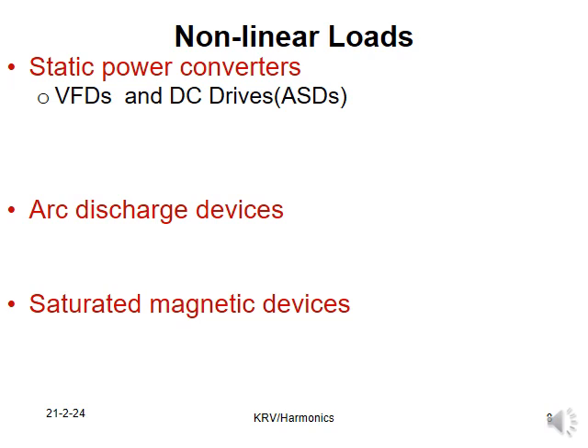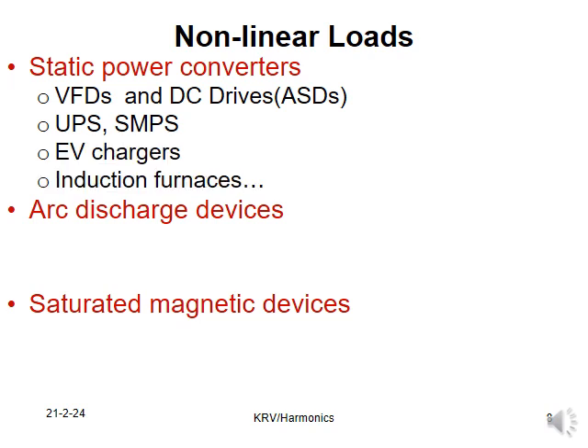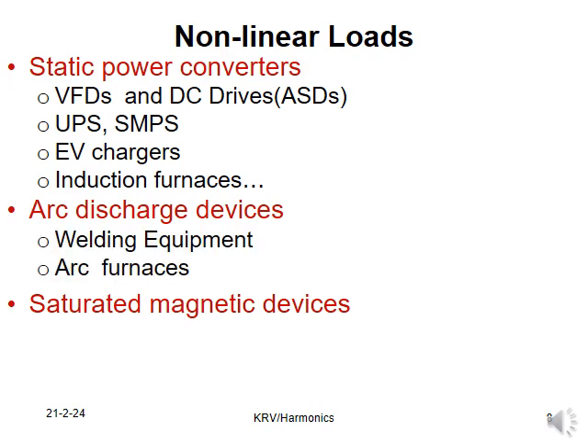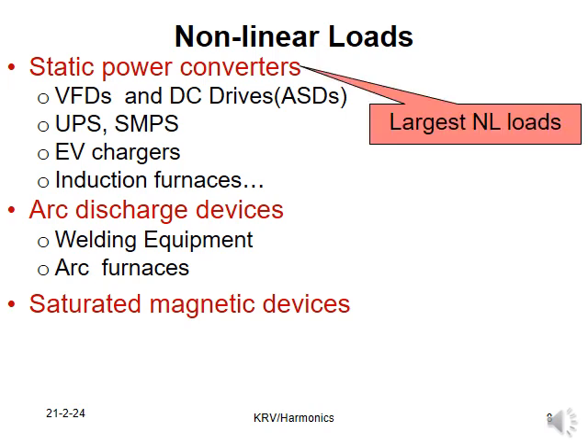Variable frequency drives and DC drives, which are generically known as adjustable speed drives, uninterruptible power supply and SMPS, EV chargers and induction furnaces belong to static power converters. Welding equipment and arc furnaces belong to the category of arc discharge devices. The static power converters are the largest non-linear loads in use today. Rotating machines to a lesser degree also produce harmonic currents.